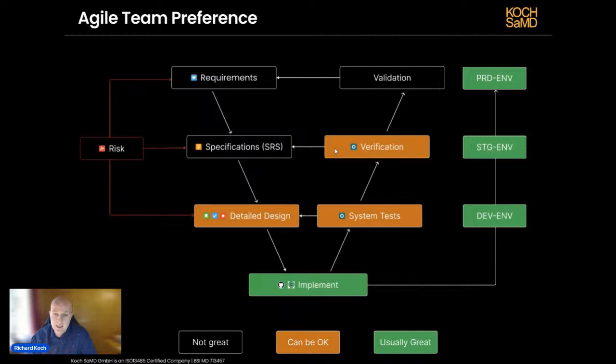So again, there is a large overhead for medical device software, as I know this audience knows. But in my experience, I've seen a lot of missing documentation. Things like 5 to 10 risks for a very complex high-risk class system, 20 requirements, 10, 20 specifications. They're done with good intentions, don't get me wrong, but there's no way that any software project, at least in my view, should have fewer than a few hundred requirements, a few hundred specs, if not more than that, getting into the single-digit thousands or more, especially if you've got a global rollout, if you start looking at global regulations.